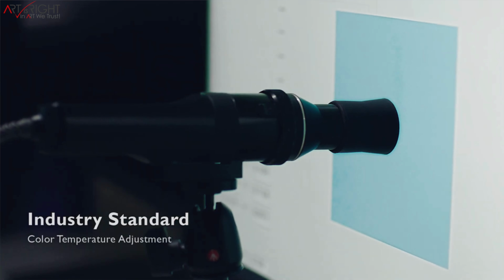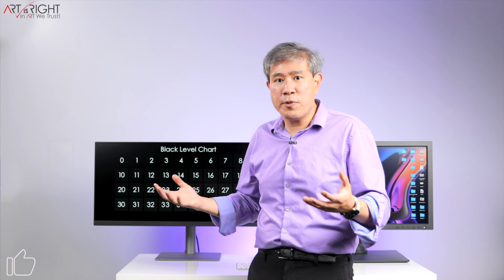The answer to this question is yes, you should always go in and custom calibrate your display. And here's the reason why. Even though the factory may be using a really sophisticated instrument to do a display calibration there, and yes, it has been pre-calibrated, and there are all these color modes you can choose from in the display, so you can choose to use those color modes.